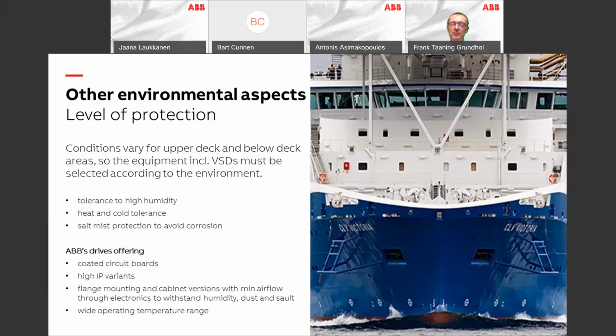It sounds technical, but what it really is: typically you would install your drives in a box, but drives produce a lot of heat. When you confine heat inside a box, you need to cool the box to avoid overheating. Flange mounting essentially removes 80% of the heating through the back side of the panel without heating the panel. Now you can reduce the cooling requirement and thereby also reduce the fuel consumption for cooling of the equipment on board. And that also helps expand the operating temperature, allowing you to have more variance.